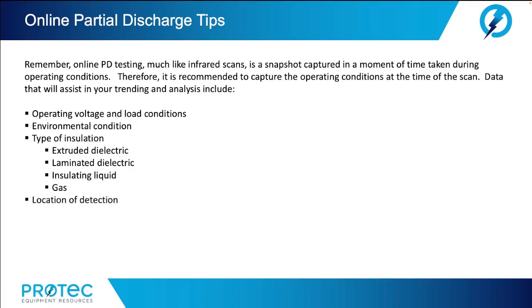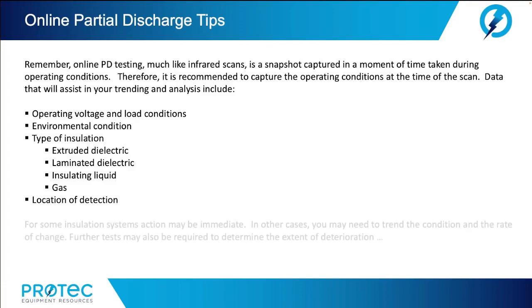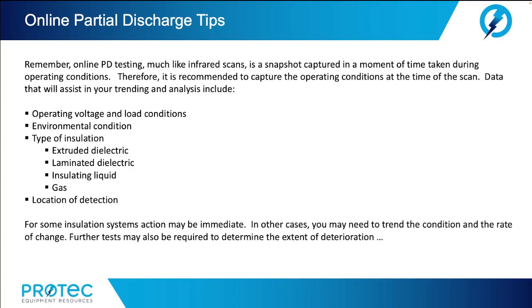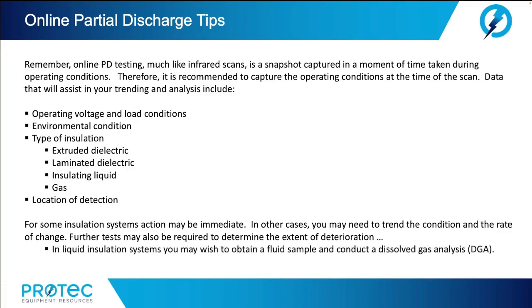Were you able to detect the location of the defect? Now, for some insulation systems, action may be immediate. In other cases, you may need to trend the condition and the rate of change. Further tests may also be required to determine the extent of deterioration. In liquid insulation systems, you may wish to obtain a fluid sample and conduct a dissolved gas analysis, or DGA. In gas insulation systems, you may wish to conduct a humidity and purity analysis.